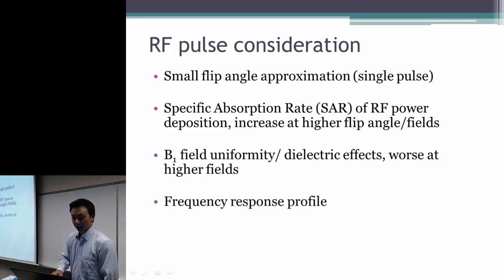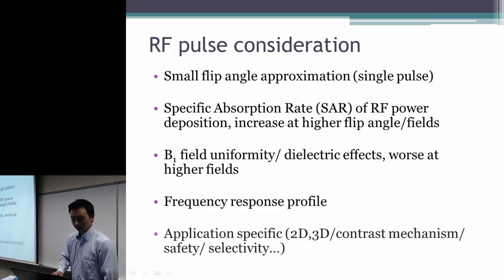And also we need to understand the frequency response profile to choose the correct type of RF pulse that meets our needs. We also need to consider what kind of application we are using, whether we are trying to do 2D or 3D, and we need to understand the contrast mechanism and also the safety and selectivity of the RF pulse itself, whether it will give us the results and image contrast that we desire.